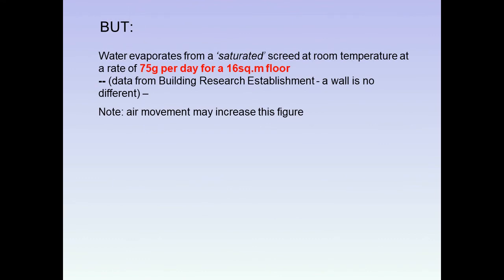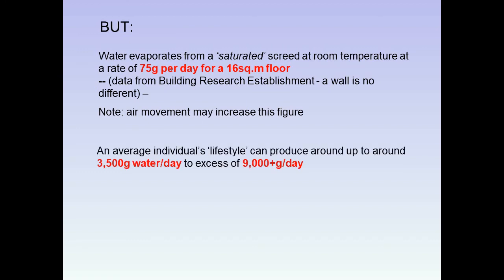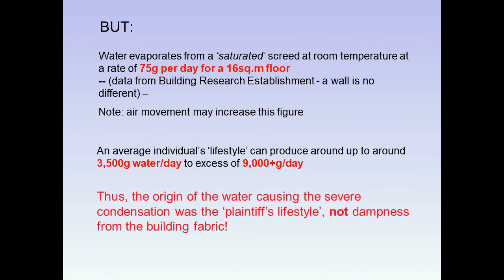Water evaporates from a saturated screed at room temperature at a rate of about 75 grams per day for a 16 square metre floor, and a wall is no different — though air movement may increase this figure. An average individual, through their lifestyle, can produce up to around 3.5 litres of water per day — i.e., 3,500 grams — and in excess of 9 litres, or 9,000 grams, per day. Therefore, the origin of the water causing the severe condensation was the plaintiff's lifestyle, not dampness from the building fabric, which was shown to be dry.